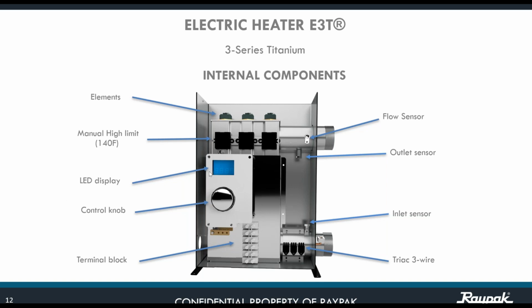You have the LED display that is going to show you incoming temperature, inlet temperature, outlet temperature, flow, and whatever message the CPU is going to be sending to that display. The control knob where you're going to be monitoring your system. The terminal block where you make the connection for the high voltage, L1, L2 plus ground. Then we have the key element on this particular heater, the TRIAC, 3 wire elements that are right here.